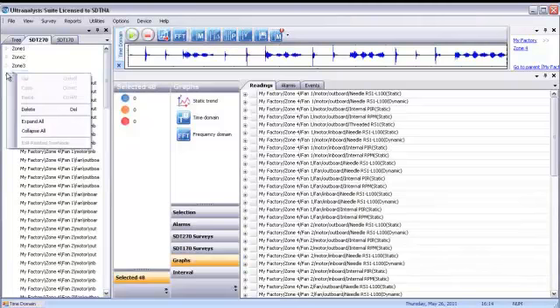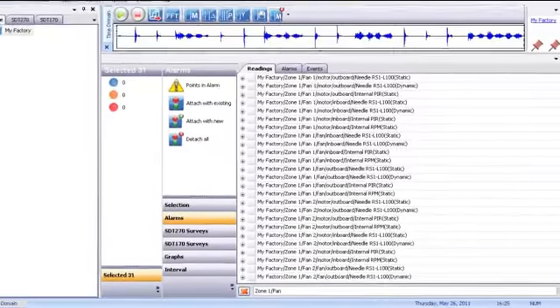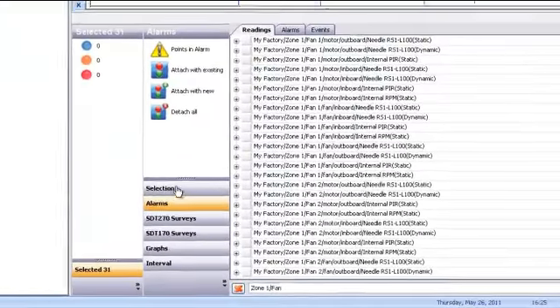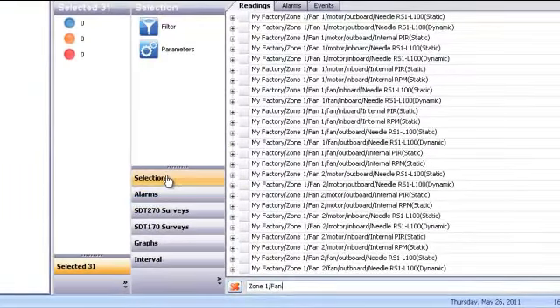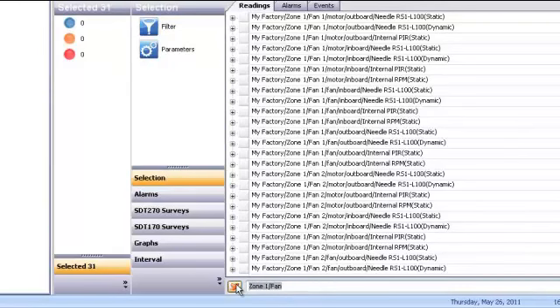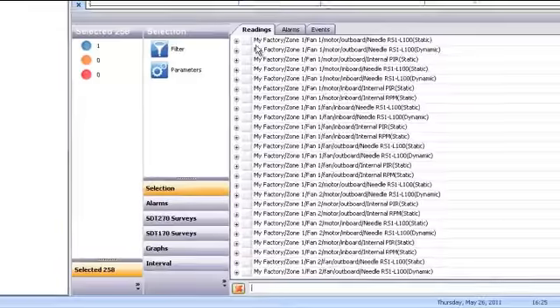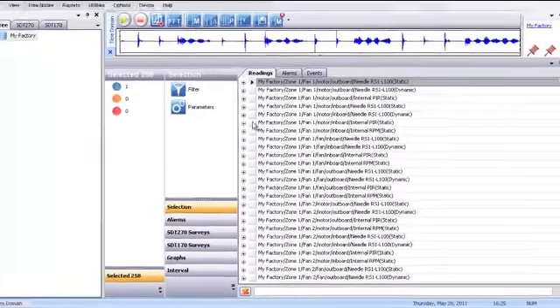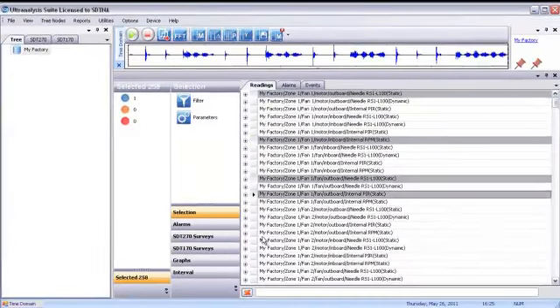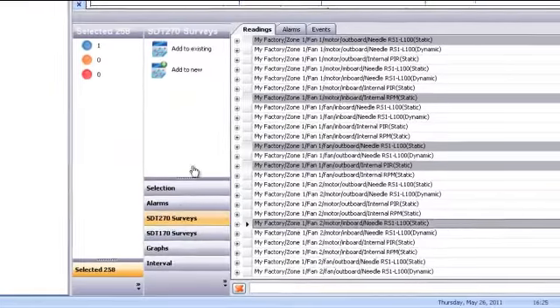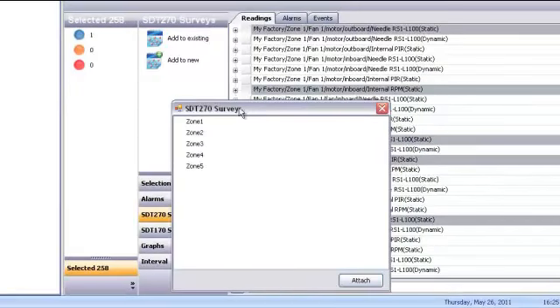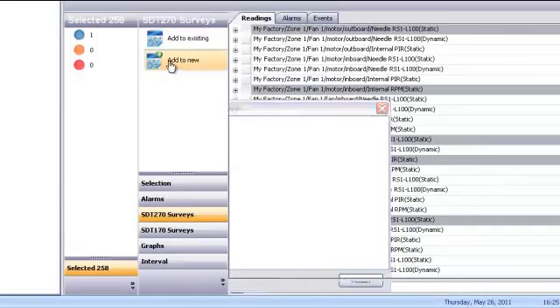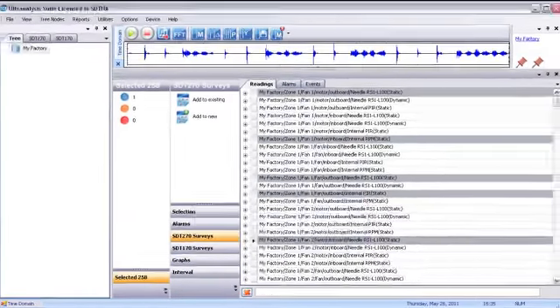You can see now we have five work orders, each with a more realistic number of jobs. Another way to build a survey is to use the selection tool in the bottom pane. By using the filtering function in UAS, you can drill down into your data tree to create custom groups of measurements. When your list is ready, click on SDT 270 Surveys button and choose Add to Existing to add measurements to an existing survey or Add to New to build a new survey.